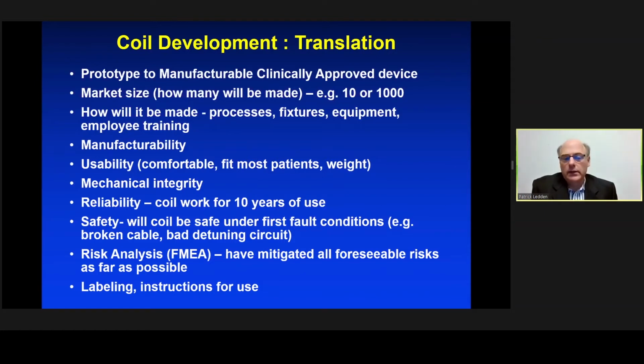Any medical device, you have to look at safety. And not only is the coil going to be safe under typical operating conditions, is it going to be safe under first fault conditions, such as a broken cable or a bad detuning circuit? Safety you can evaluate in terms of risk analysis. And in particular, you'll need to show that you mitigated all foreseeable risk as far as possible. While not necessarily part of the coil design itself, you've got to look at labeling, instructions for use. These are important, and actually in some cases can be used to mitigate risk.